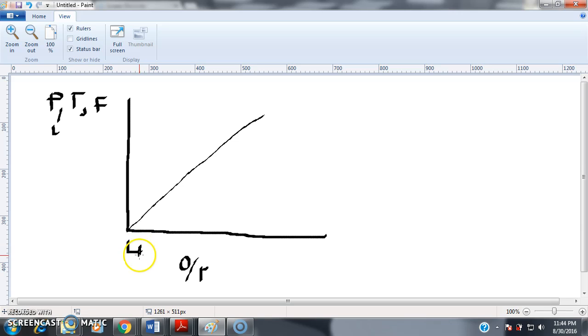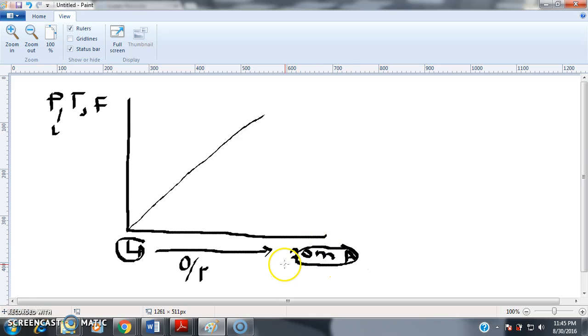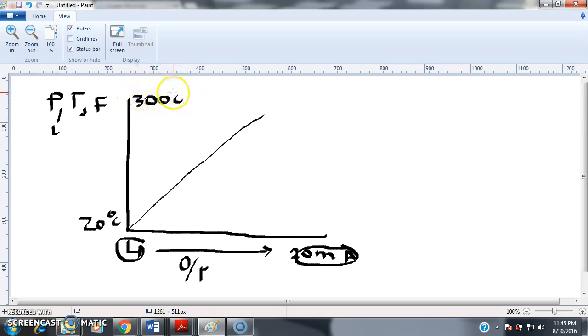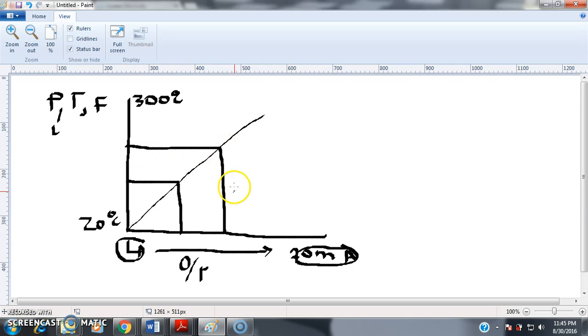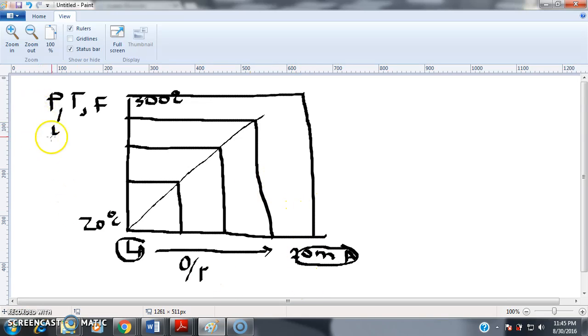From the RTD specifically, we're getting a current signal that goes from 4 up to 20 milliamps. At room temperature we should get 4 milliamps, and the maximum temperature gives us 20 milliamps. Anything in between, using this graph or the formulas, you can get the relative temperature. The maximum 20 milliamps corresponds to the maximum temperature.